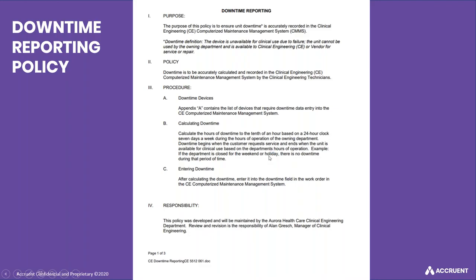Downtime begins when the customer requests service and ends when the unit is available for clinical use based on the department's hours of operation. So an example, if the department was closed for the weekend or holiday, there's no downtime during that period of time. I will tell you that over time, we updated this policy. And the reason we started here is you have to start with an apples to apples comparison, right? So we went through our existing contracts and what the language was around measuring downtime, and we followed that just so that we were comparing apples to apples as we started. But then we moved beyond it.